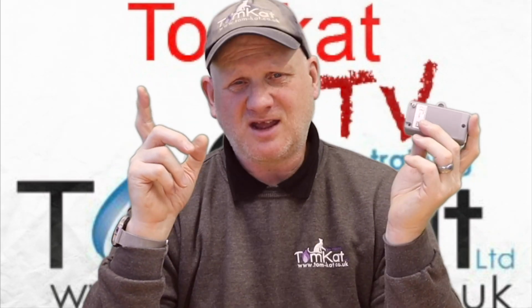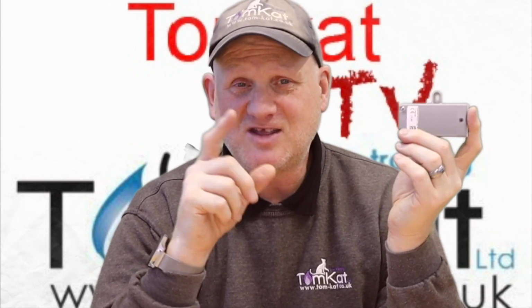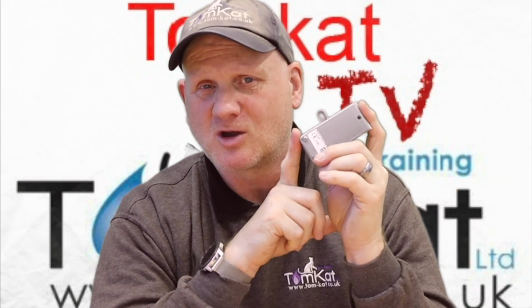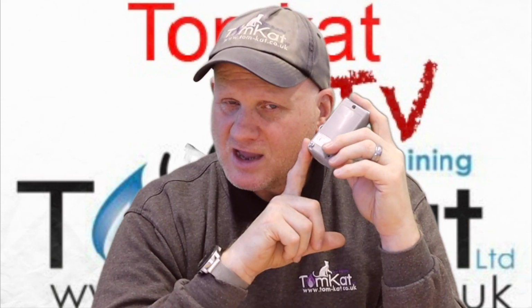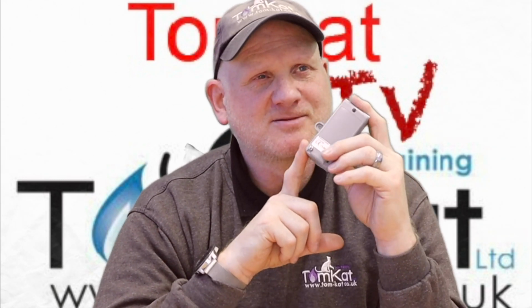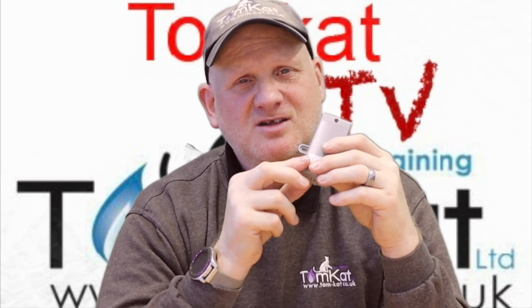Now, these aren't new things. These have been out a long time. I think 10, 15 years ago, Viessmann were putting these in the box, and they still do. Every Viessmann boiler you buy will come with weather compensation, and it should be installed. But one of the things we have found out about these is customers don't get used to them. And in the past I've had to come and disconnect a few of these because the customers have insisted on it, because these stop the boiler firing up.